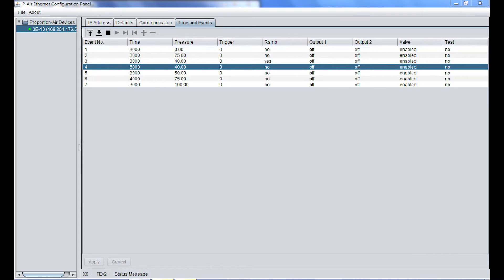The time, illustrated in milliseconds, is in this column. The column labeled pressure is a percentage of command that you're looking for. In this case we are stepping through 0 to 100% command, which in turn gives us a 0 to 10 volt single ended output.